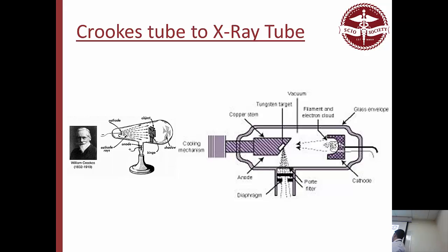Okay? So the first part right here, to make the electron cloud, you have to give some energy to the tungsten. So all you do is basically run a really small voltage circuit. This is called a low tension circuit. So you run a little bit of voltage through the tungsten filament. This heats up the tungsten. We know that happens in light bulbs all the time. As it heats up, electrons come off the tungsten because heat causes them to fly away from the atom, if you can picture it, and they hover in that region. They're ready to go. Okay?